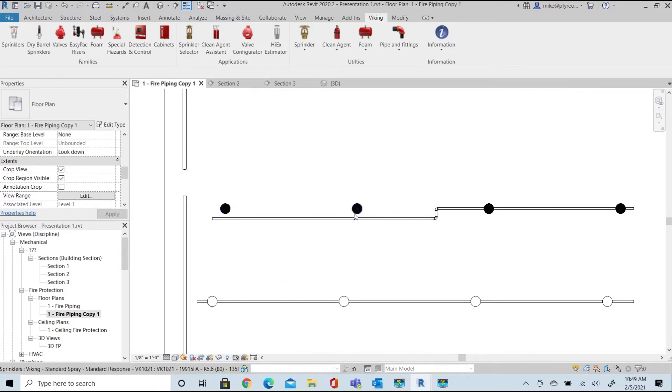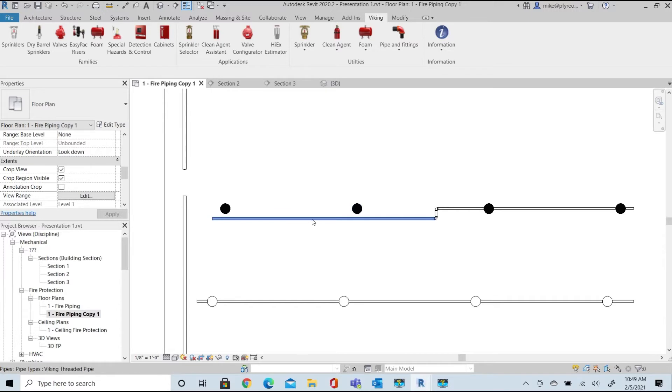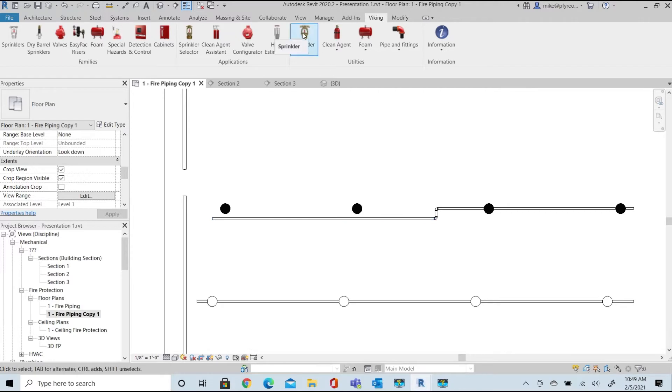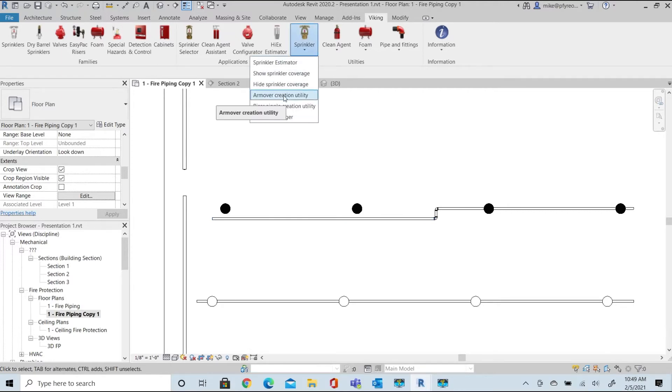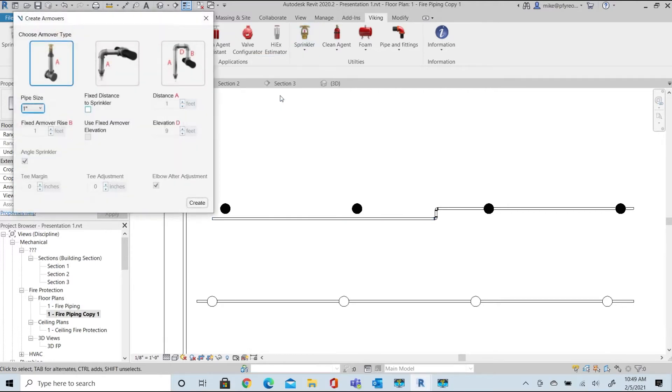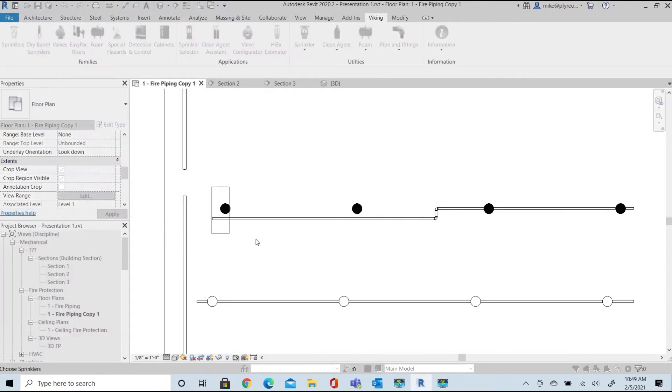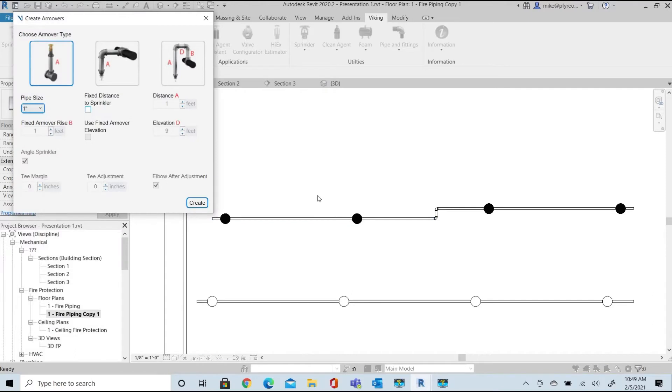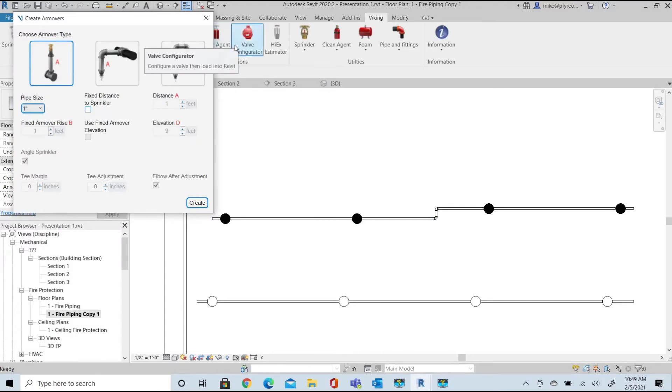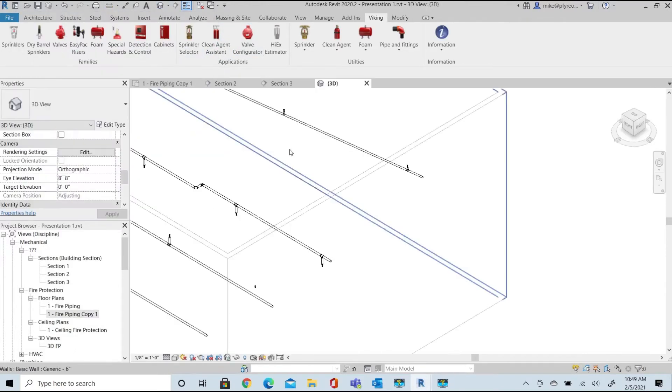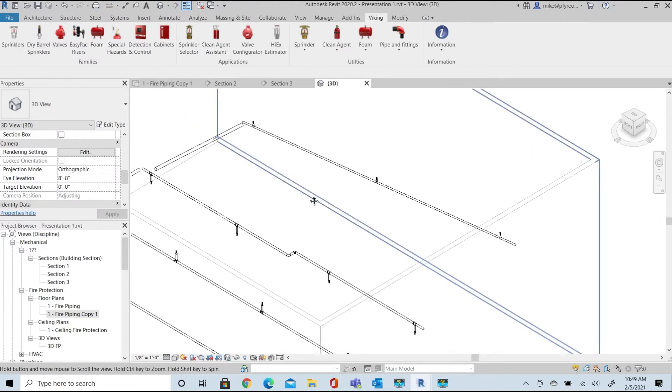Let's look at one other example of connecting pendants. Notice that the sprinklers are offset from the branch line. With this tool, the branch line location is the dominant factor, and the sprinklers will relocate to the branch line. To connect piping to the sprinkler head location, the pipe must be located directly above or below the sprinklers desired.